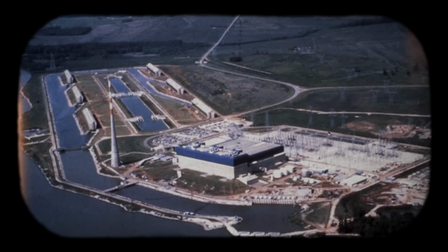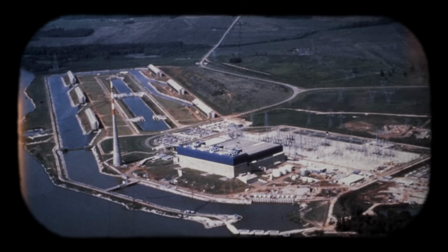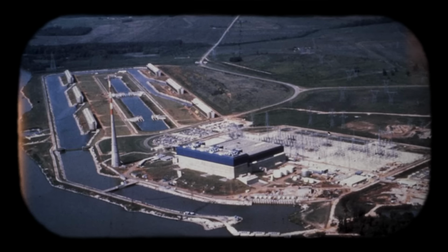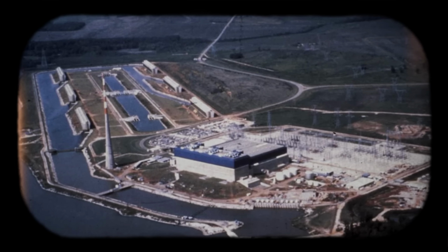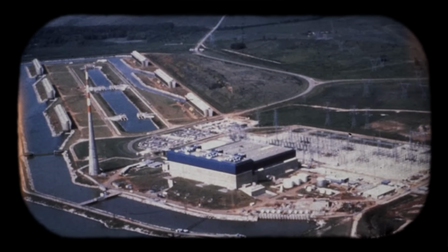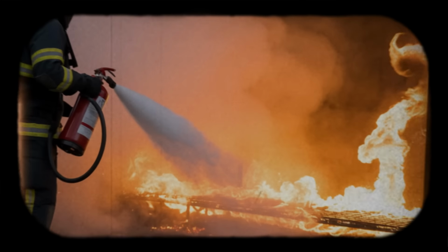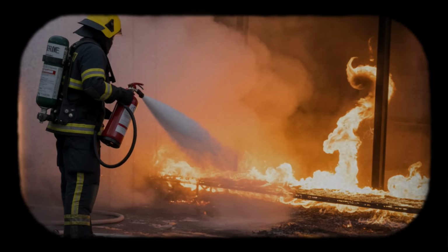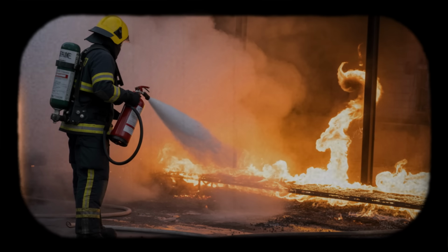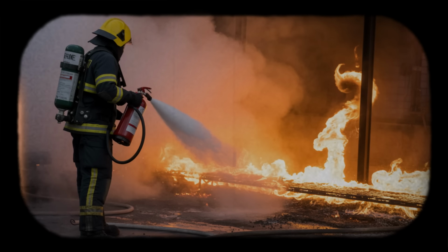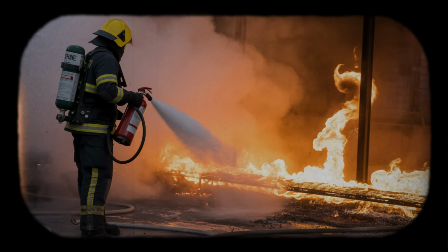If the fire spreads an additional 3 to 4 cable trays westward, it will reach circuits controlling alternate shutdown cooling methods. Emergency procedures provide for use of other systems. Core spray can be operated in a cooling mode. Feed water can be established to maintain level. Even control rod drive hydraulics could theoretically provide some makeup flow. But all of these alternatives require functioning instrumentation to operate safely and effectively.